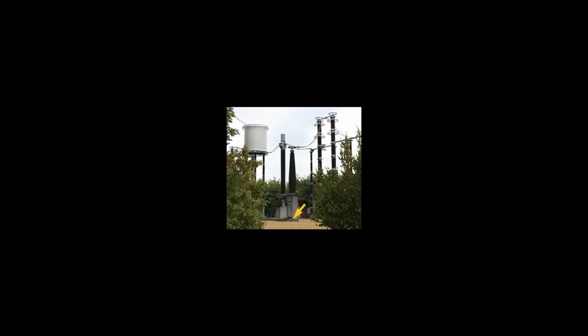Steel tank valves. For larger valves, a steel tank with ceramic insulators for the electrodes is used, with a vacuum pump system to counteract slight leakage of air into the tank around imperfect seals. Steel tank valves, with water cooling for the tank, were developed with current ratings of several thousand amps. Like glass bulb valves, steel tank mercury-arc valves were built with only a single anode per tank, a type also known as the ignitron, or with multiple anodes per tank. Multiple anode valves were usually used for multi-phase rectifier circuits, with 2, 3, 6 or 12 anodes per tank. But in HVDC applications, multiple anodes were often simply connected in parallel in order to increase the current rating.